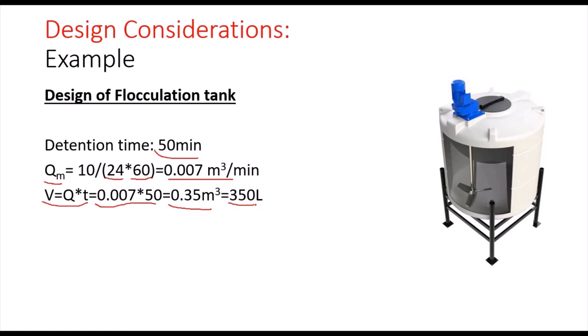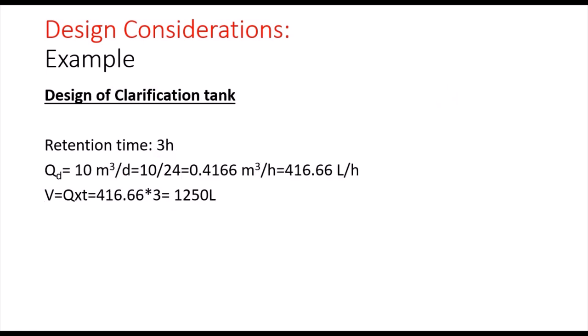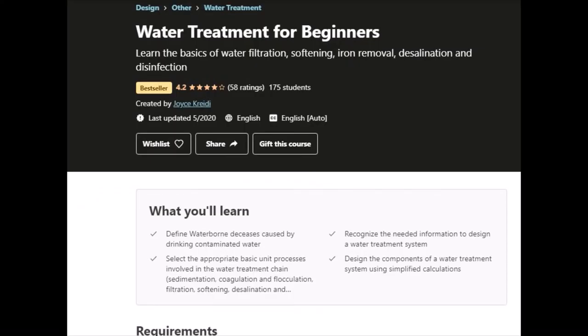This is concerning the flocculation tank. Now concerning the design of the clarification tank, which is the sedimentation tank, the retention time we have chosen is three hours. So Q is 10 cubic meters per day divided by 24, which is 0.42 cubic meters per hour or 416 liters per hour. And also here we have to use the formula Q times t for the volume, 416.66 times 3. So the volume of the clarification tank will be 1250 liters.